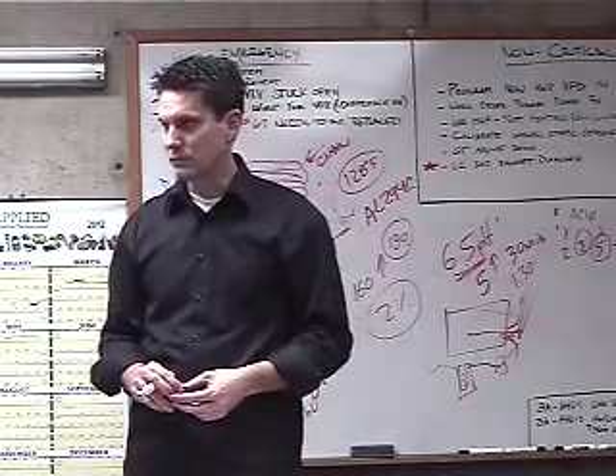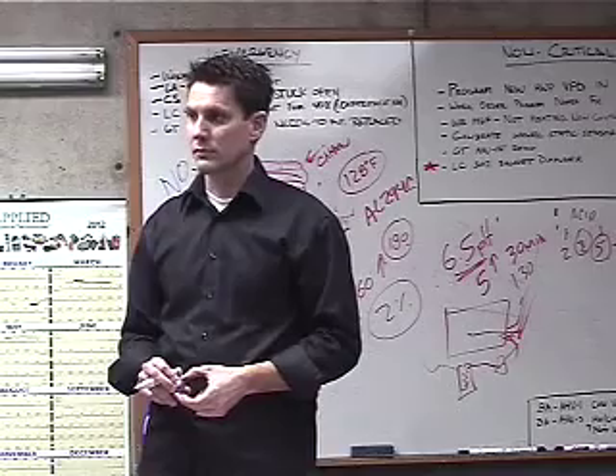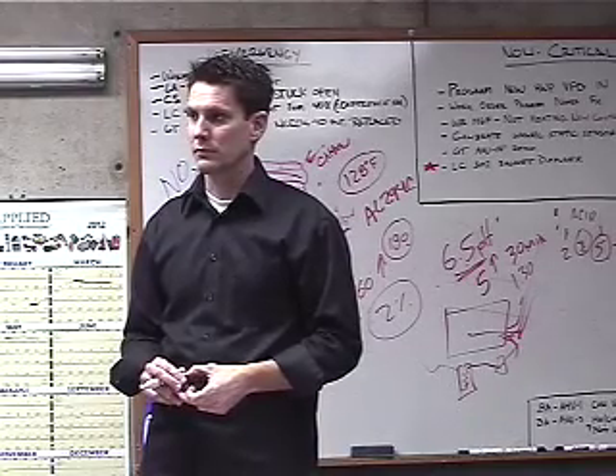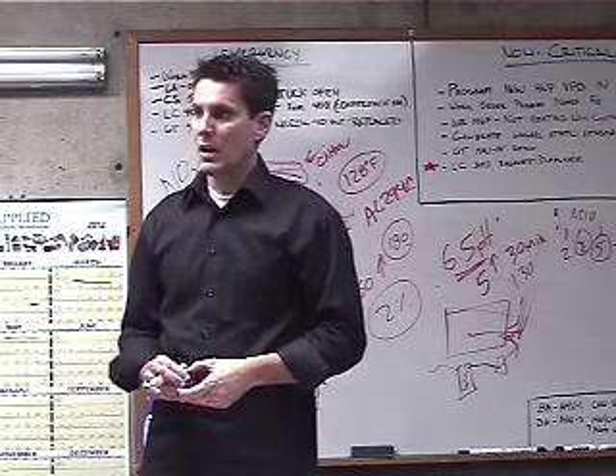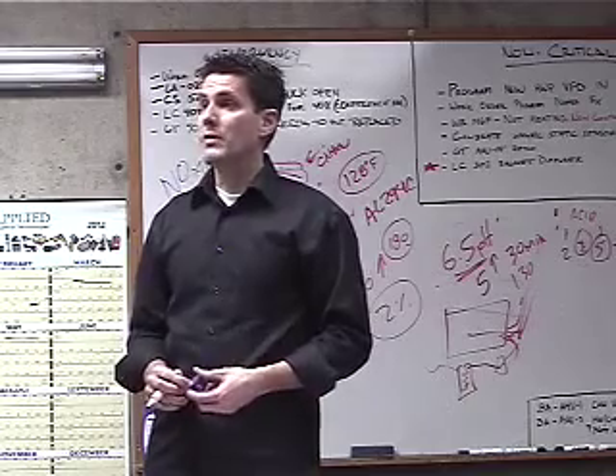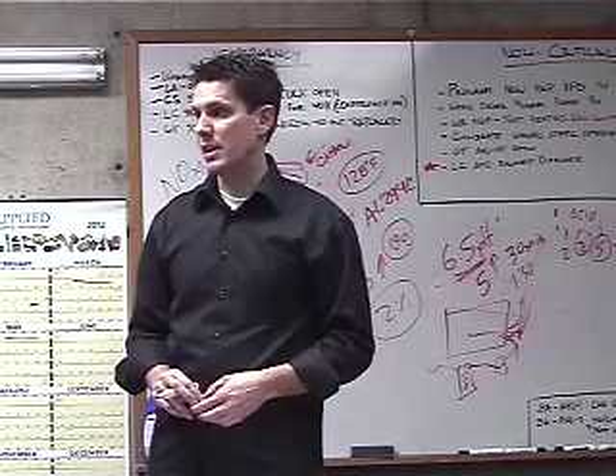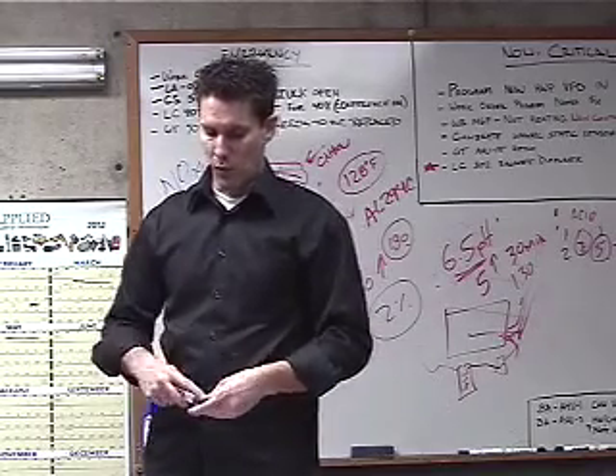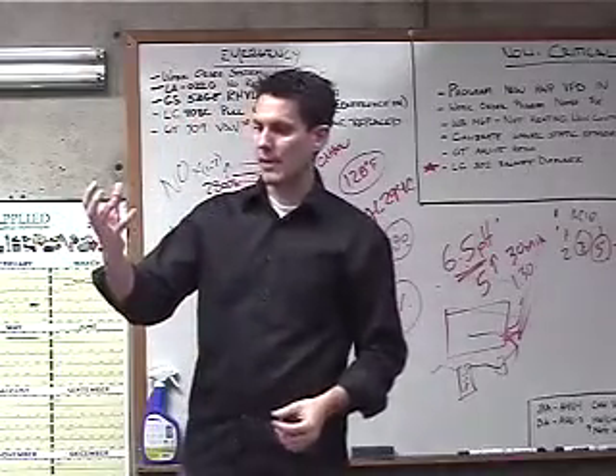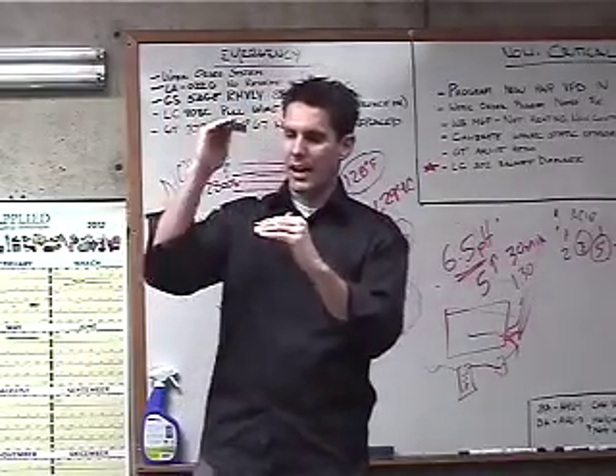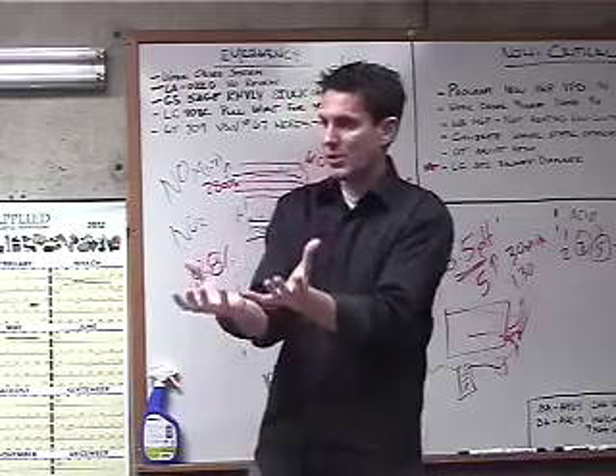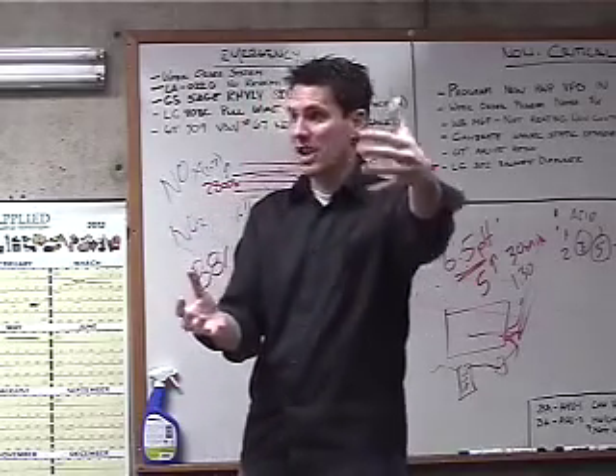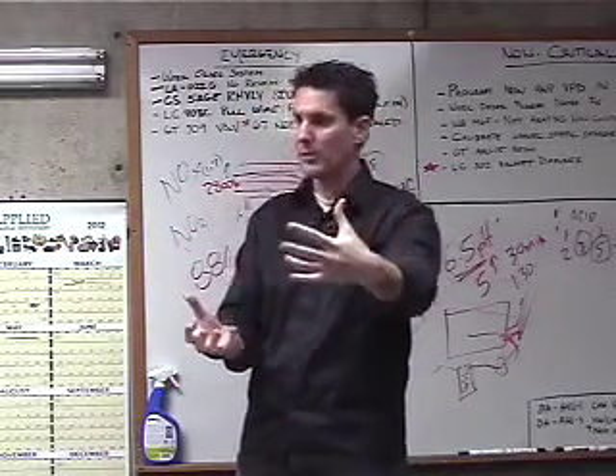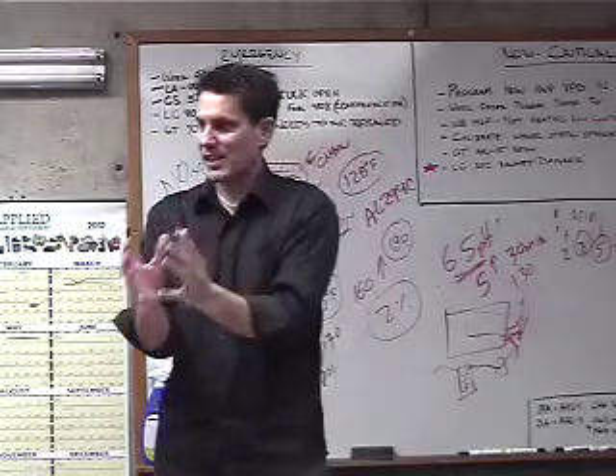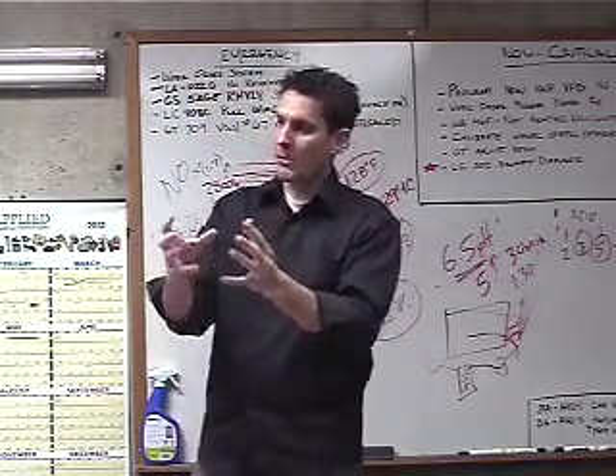What if the fan on the flue regulate how much outside air is coming in, or is it just has nothing to do with that? The fan that you've got here on these boilers is at constant speed. So what you've got on this boiler is we dialed it on at high fire. So okay, we want 8% CO2, which means I need so much excess in that 10-to-1. So 10 volumes of air for 1 volume of gas. So I set that up at high fire. Then we set that up at low fire.